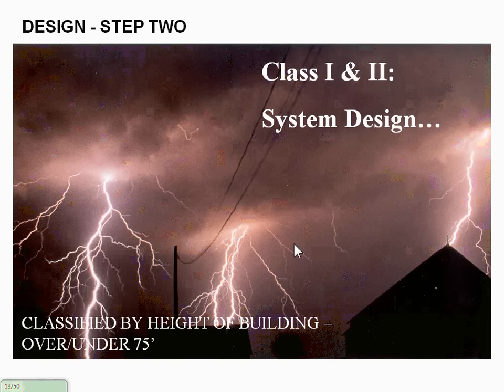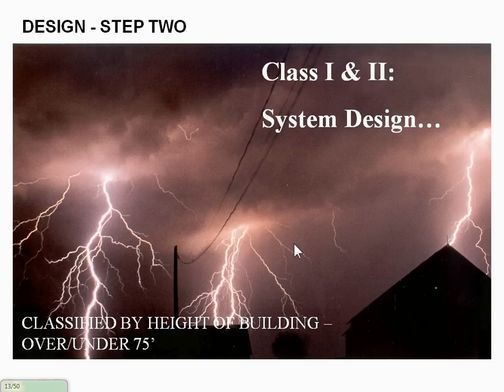So the first thing you have to decide for your building is whether it's a class 1 or class 2 system. That's basically determined by whether your building is over or under 75 feet in height. When you get over 75 feet, you need a larger cable size than a smaller one, because lightning has to travel a further distance. 75 feet is the cutoff — they've done lots of experiments and tests on this. Your buildings are always under 75 feet, I think, so it's a two-story building, meaning your system would be considered a class 1 structure.